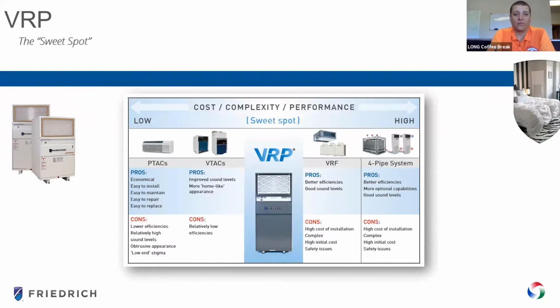And here's kind of the general overview of where this unit came to be. On the left side, you have your kind of standard PTACs and VTACs. One of the benefits of these, they're typically economical. They're easy to install, easy to maintain and repair. Some of the cons that generally come with these are the efficiencies. Generally, they're single speed scrolls, so your compressor is either fully on or off, and also the noise. And one other con is that people generally view them as a little less high end, like a lower end hotel if you're staying in one with a PTAC or VTAC.